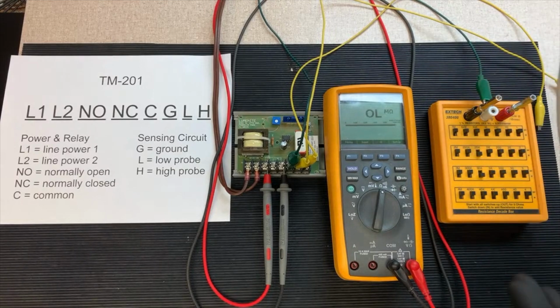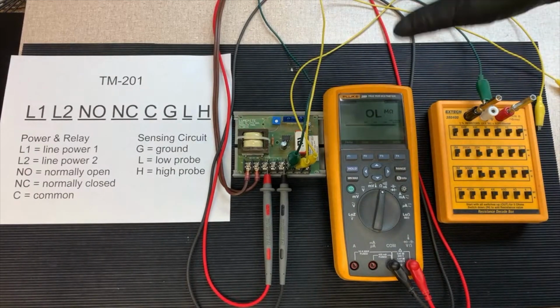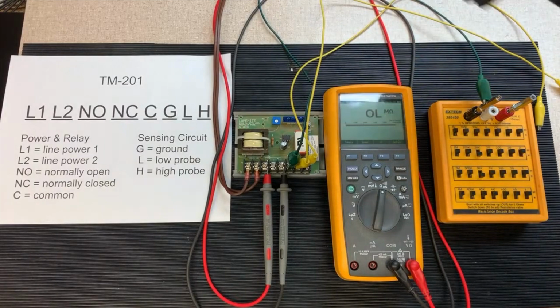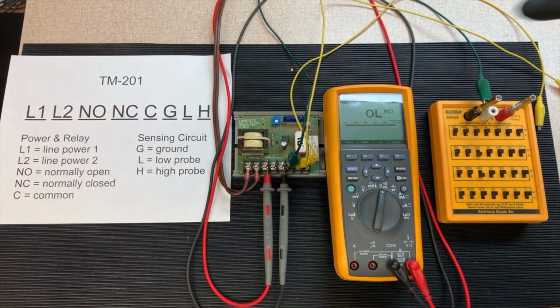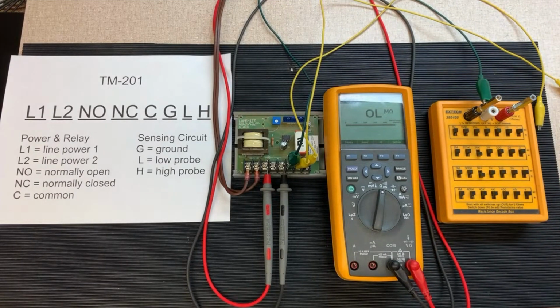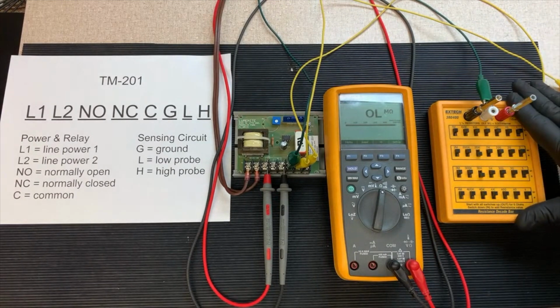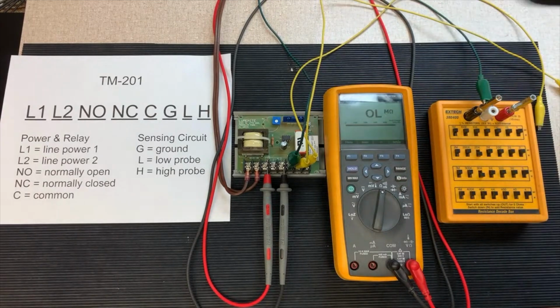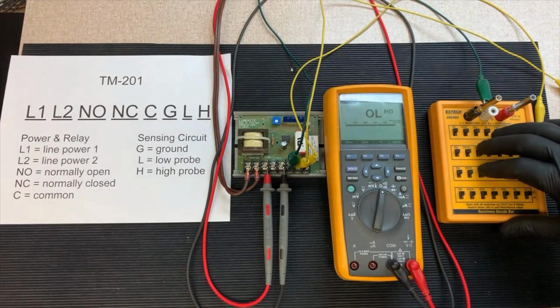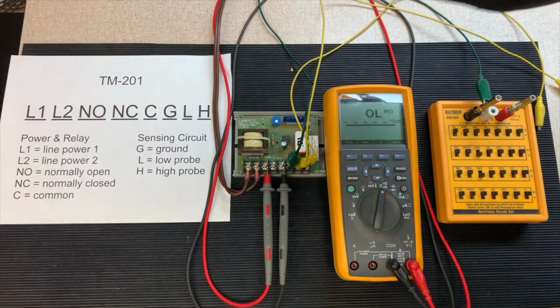And this happens with conductive liquids. Obviously, if the resistivity of the liquid gets too high, it makes it more non-conductive. Like for instance, oil, this would not work. But with water, it works perfectly fine because water is very conductive. We're just using our substitution box in this case to show what's going to happen at 50K. So 50,000 ohms resistivity. Let's do this first.